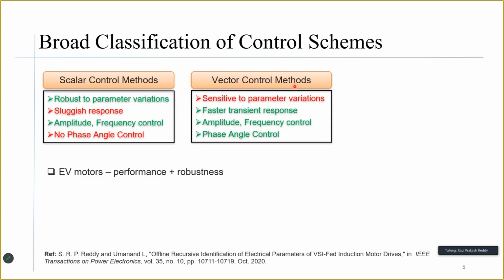But on the other hand, we do have vector control techniques, and vector control techniques differ from scalar control techniques in terms of the improved torque dynamic response, right? The torque response of the vector control based induction motor drives is really superior when compared to its scalar control counterparts, mainly because of the inclusion of phase angle control as well in the vector control techniques. So since all three quantities, namely the amplitude, frequency and phase of the stator voltage, are controlled in the case of an induction machine while using vector control techniques, it results in superior torque transient response characteristics, which is what is lacking in scalar control techniques.